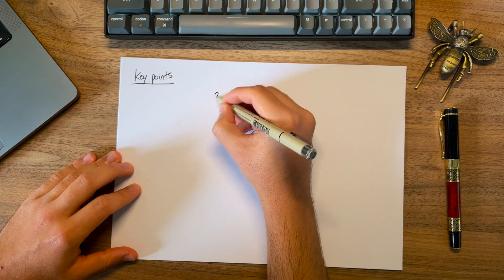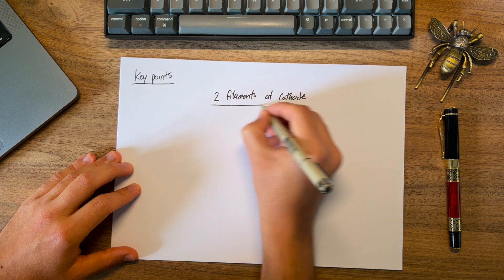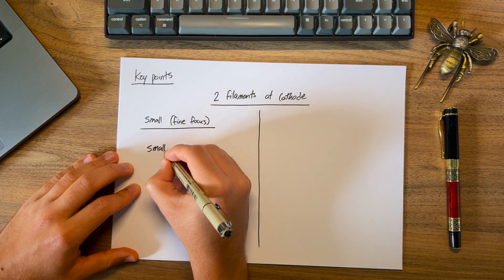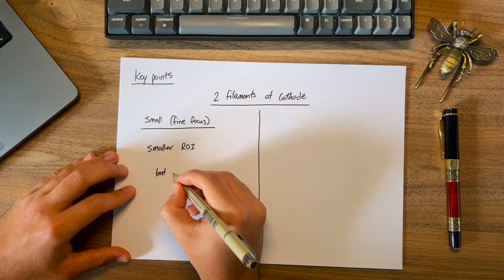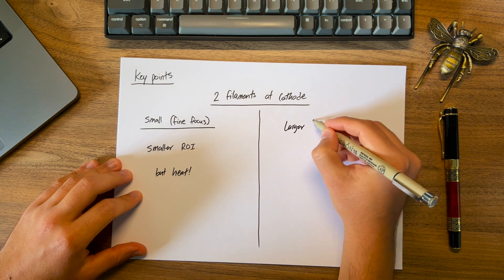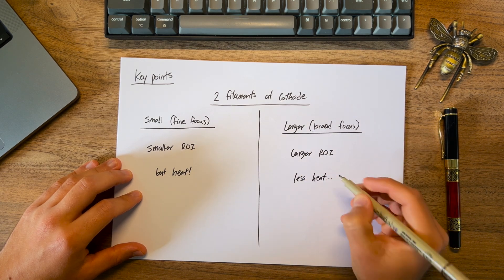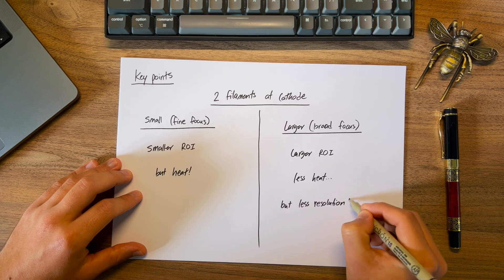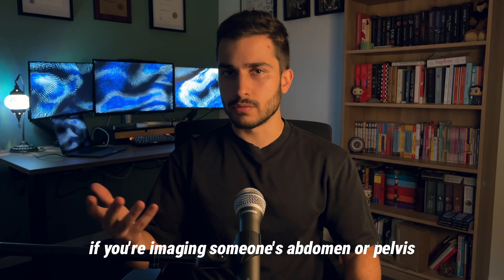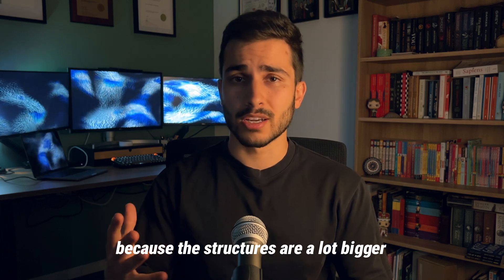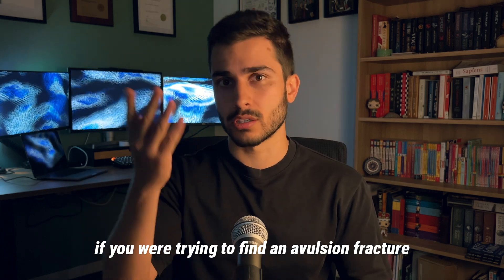So what have we learnt? The cathode has two filaments: a small and a large. The small one — aka fine focus — is used for smaller areas and results in better resolution, but at the cost of heat and tube degradation, meaning the anode surface gets disrupted which can interfere with x-ray production. The large filament — aka broad focus — is typically used for larger areas with reduced heat impact on the anode, but at the cost of some sharpness. If you're imaging someone's abdomen or pelvis, you don't really need fine resolution, unlike when trying to find an avulsion fracture in someone's finger.